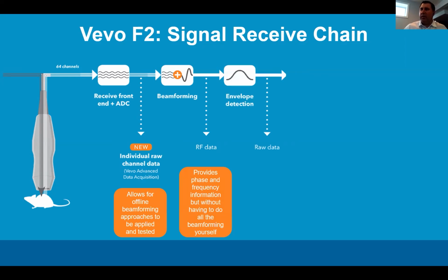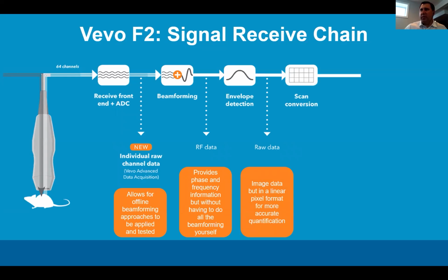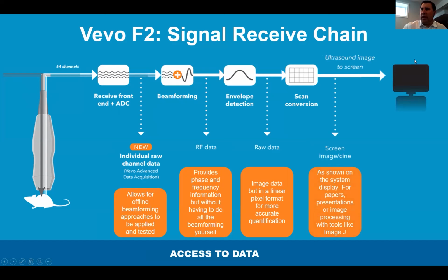From there, we continue through our signal path with many of the features of any standard ultrasound system, the ability to do standard beamforming. We do still support the beamformed RF, as we always have on our previously launched systems. So if you're not necessarily interested in the individual channels, but you want phase and frequency information without having to do all the beamforming yourself, you can certainly still collect this RF data. We have then envelope detection, the ability to collect raw data, and finally the scan conversion, which is what goes to the screen, those images that I just showed you. So if I can put this all together, this whole system is really based around having access to these various points along both the transmit and receive signal path, and ultimately at the endpoint, having that very high quality image, which you expect and need and require, especially for some of these small animal models that are being imaged.